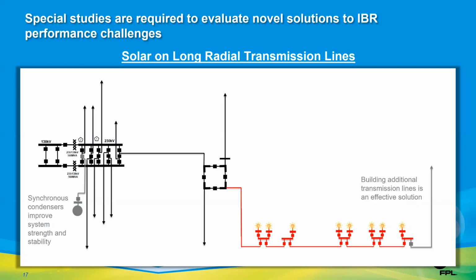Another solution is to install a synchronous condenser nearby. This improves the system strength, it relieves stability concerns, but it's also an expensive solution, especially for a situation like this where we didn't have any voltage issues. We didn't need the reactive support. We were installing the synchronous condenser solely to improve the system strength. Next click, please.